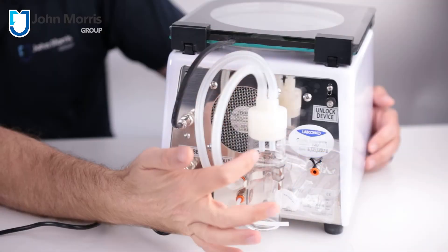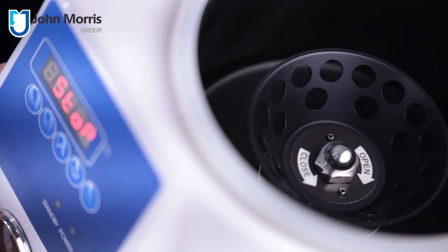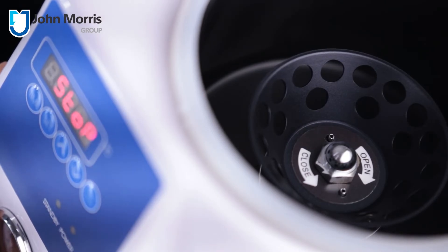This product is perfect for tight spaces and the budget conscious. It's a personal-sized centrifugal vacuum concentrator which includes a built-in vacuum diaphragm pump, glass trap, and, surprisingly, an infrared heating lid to shorten process times. The entire package weighs under 10kg and it's perfect for proteomics, genomics, genetics, cell biology and drug discovery labs. Also included is a rotor for 24×1.5ml samples and a micro strobe light to view samples while the rotor is spinning — in short, everything you need to get going.